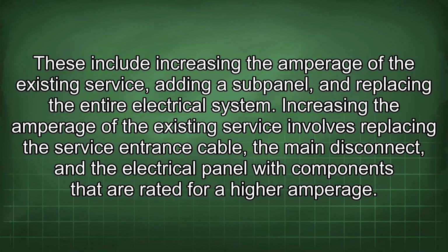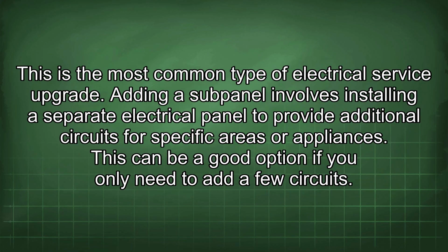Increasing the amperage of the existing service involves replacing the service entrance cable, the main disconnect, and the electrical panel with components that are rated for a higher amperage. This is the most common type of electrical service upgrade.